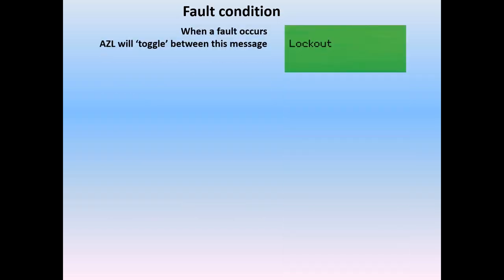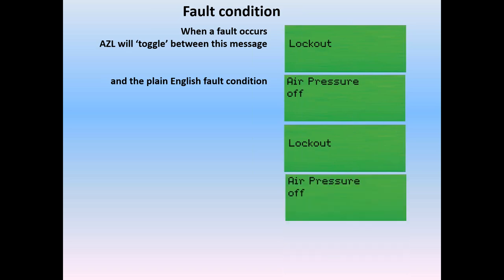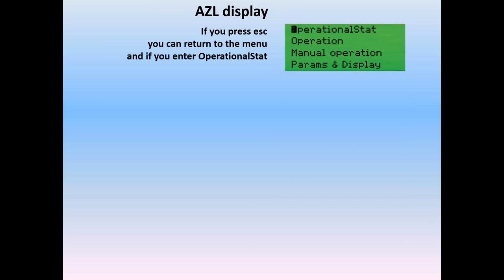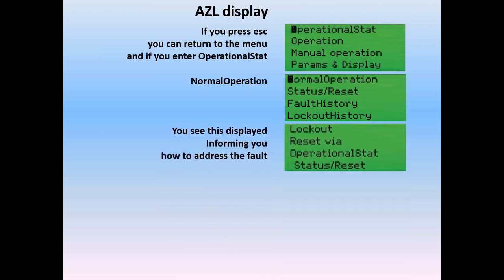When the LMV goes into a fault, the AZL screen will display a lockout and it will toggle between the lockout and a plain English fault condition — such as 'air pressure off' — back and forth, telling you what the fault condition is. On the AZL display, if you press escape, you can go back to operational status. When you go to try and enter normal operation, it says you can't because you have a lockout and you must reset via the operational status reset screen, specifically telling us how to go about resolving the fault and resetting it.